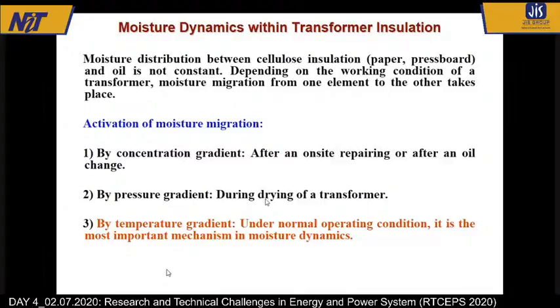But what happens every day is called the temperature gradient. As the temperature goes up and comes down, it has now been established conclusively that moisture moves between paper and oil. When the temperature increases, moisture moves from paper to oil. When the temperature decreases, moisture moves from oil to paper. The interesting part is that the time constants of these movements are different. The moisture moves from paper to oil at a faster rate, but from oil to paper at a slower rate. Now, this has an important bearing.